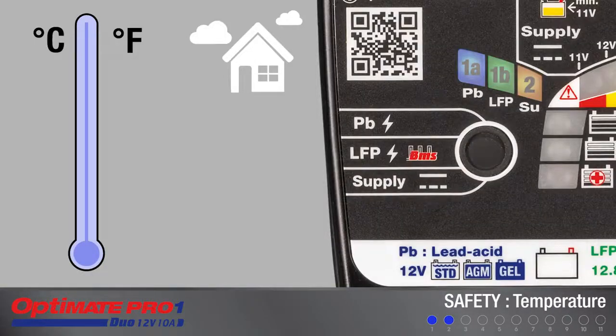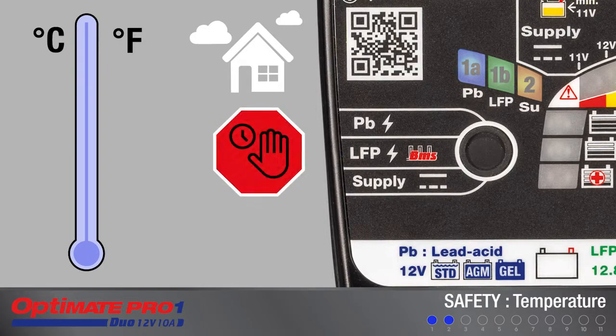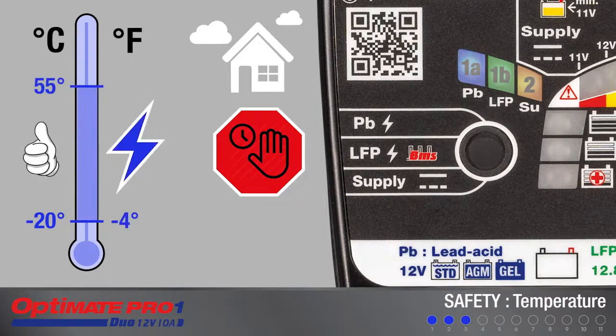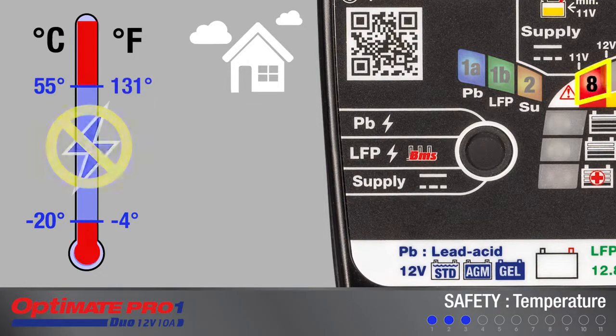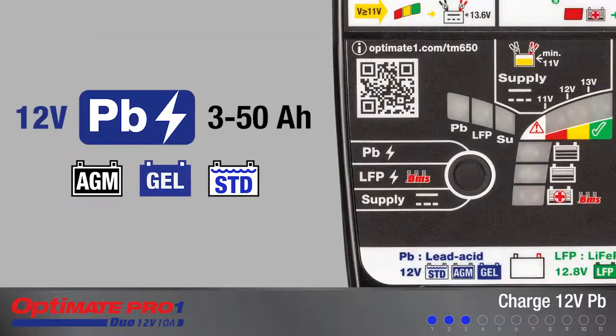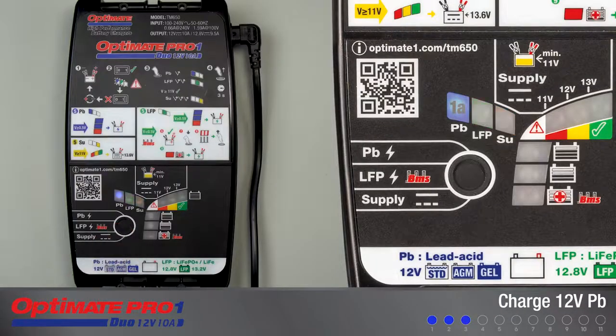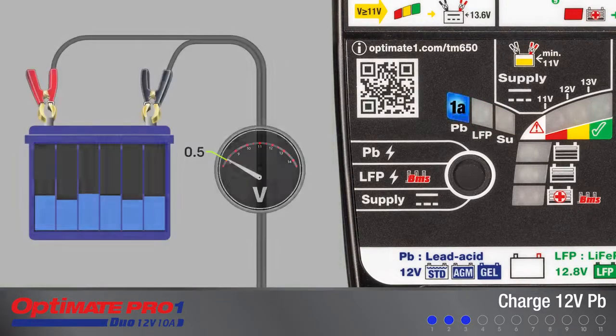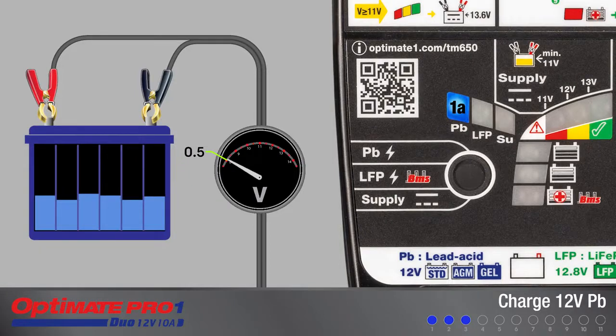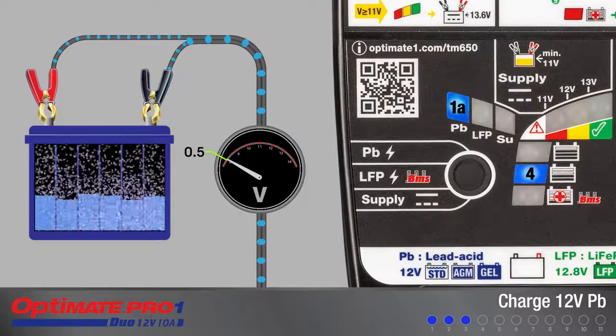Before a charge current is delivered, the ambient temperature is measured. Charging will proceed normally if the temperature is between -20 and +55 degrees centigrade, or -4 and +131 degrees Fahrenheit. Otherwise, LED 8 will blink rapidly, indicating no charge will be delivered until the temperature is within this range. For all 12-volt lead-acid batteries, select PB charge mode. If the connected battery's voltage is 0.5 volts or higher, charging continues automatically. LED 3 or 4 will turn on depending on the condition of the battery.